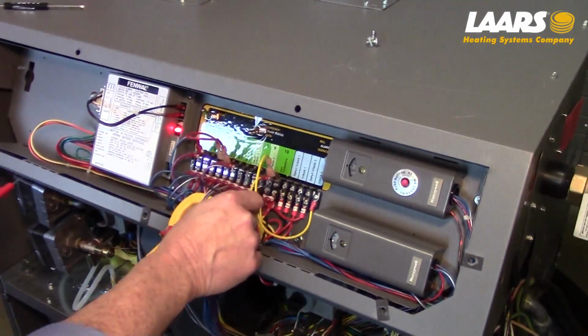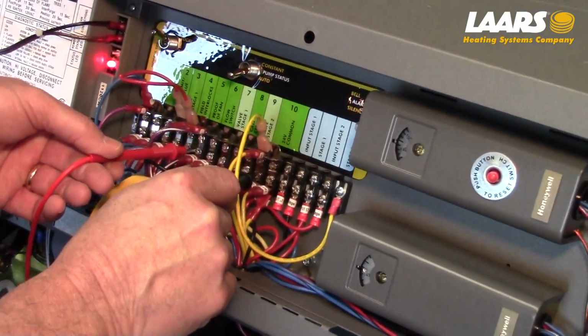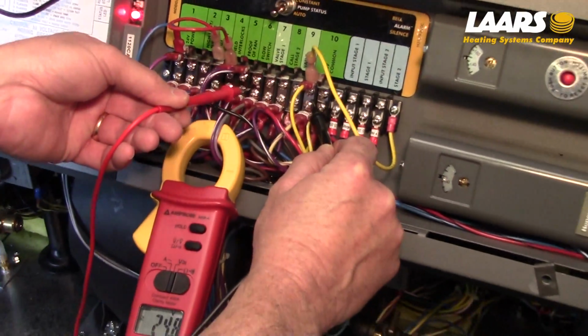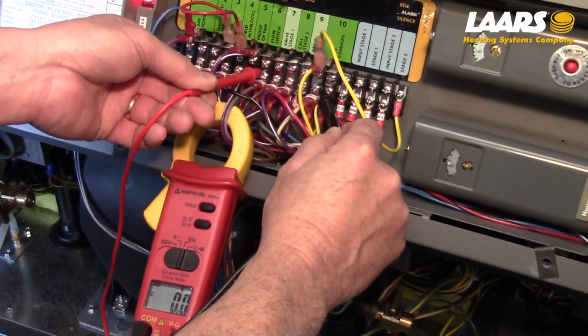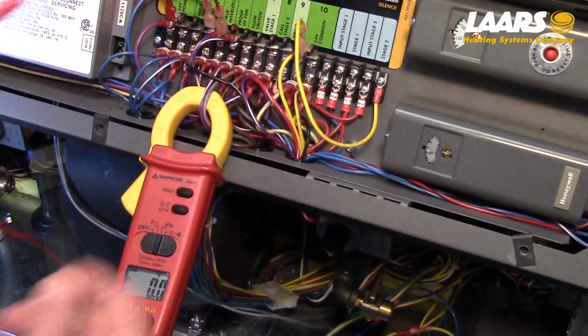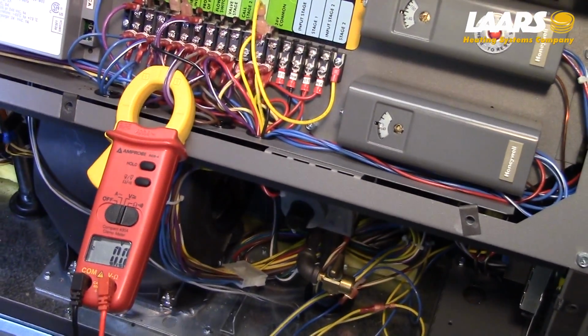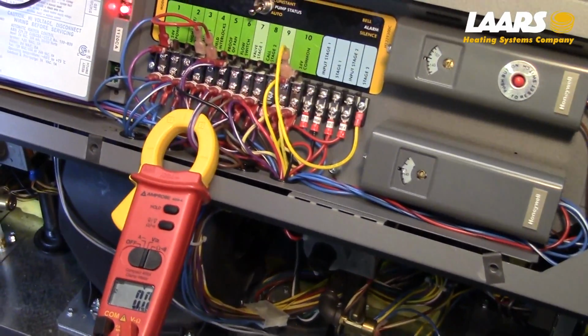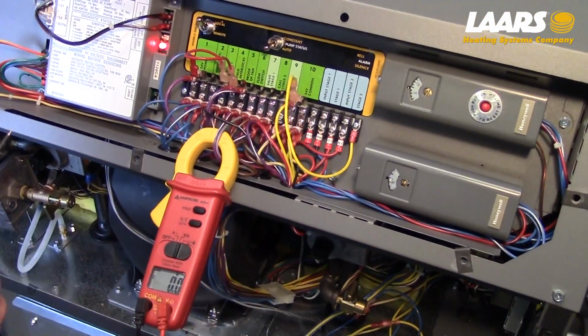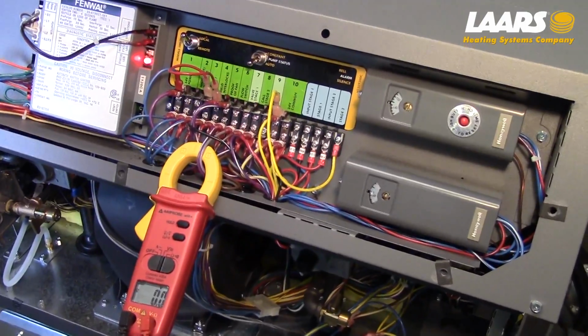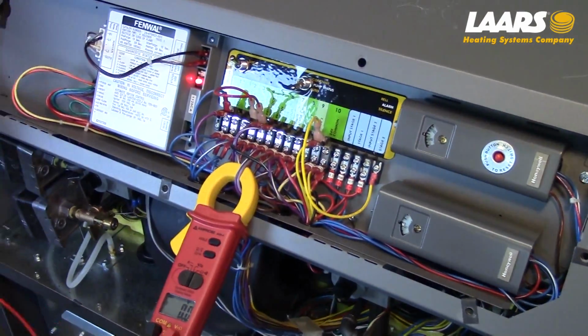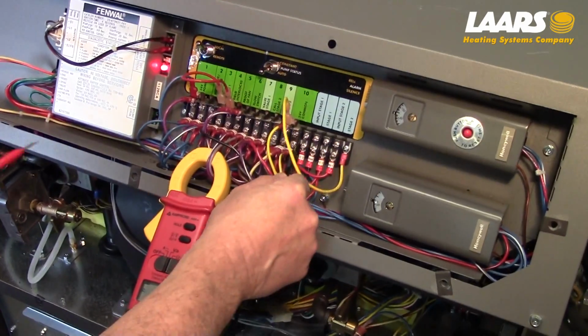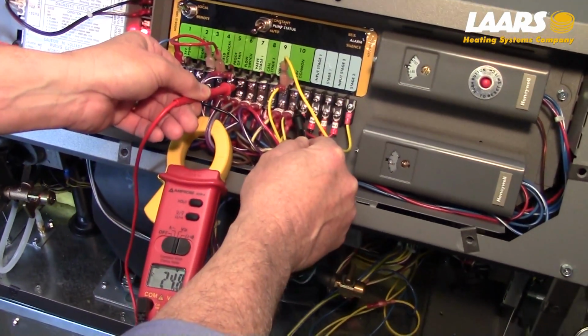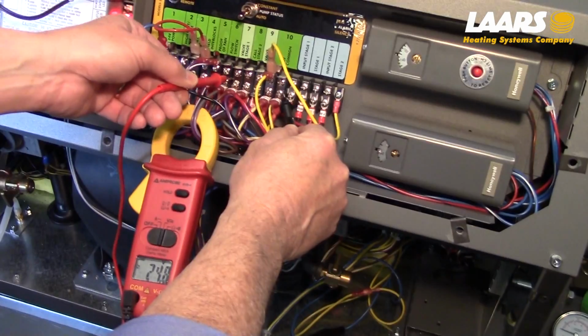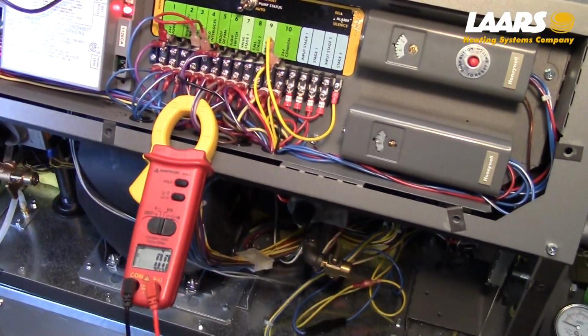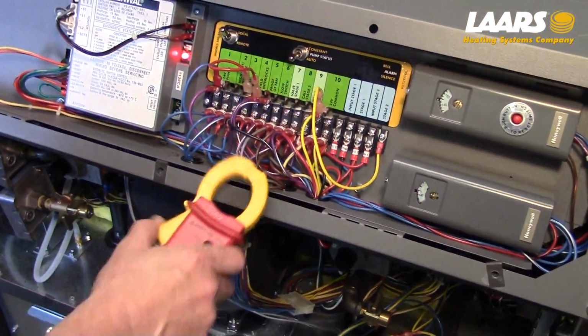Next, we're going to walk across. The boiler still doesn't fire, so I have it here at proof of fan, but I do not have it at my flow switch. Alright, that means something's going on with the pump, the coupling, the flow switch paddle. Double check to make sure your pump is running, etc. Alright, in this example, I left our pump off, so I'm going to power up our pump. So now, I have my flow switch made, which now I'm going to start going in for a call for heat. Okay?